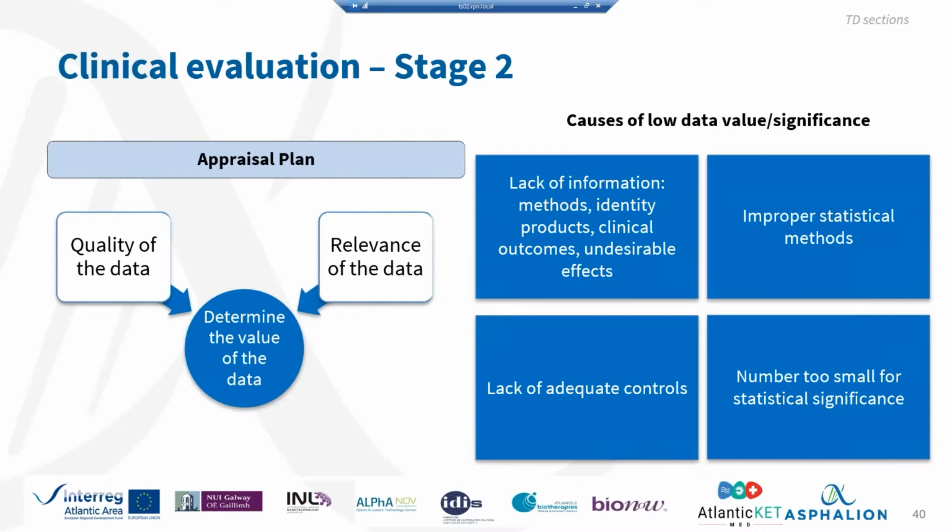this data. Okay. For instance, a clinical investigation you have performed with your device for the intended use is going to have a very high score because it's quite relevant to your device. Obviously, it's been specifically tailored to your device, so it has a lot of weight. On the other hand, a publication that is related to the current state of the art of the treatments used for a similar indication to yours, even if it's a super nice publication with a lot of quality, is not going to be super relevant. So it's not going to have a high score.